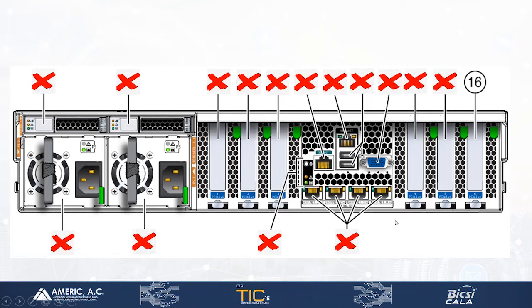Now, fundamentally, we've done away with all that, because on an OCP server, which I'll show you in a minute, the only thing on the back is a DC direct current clip, so that when you push the server into the rack, it just clips onto a 12 volt or 48 volt DC busbar. You never go to the back of an OCP rack to do maintenance — everything is done from the front. So that's what I mean about reinvention.